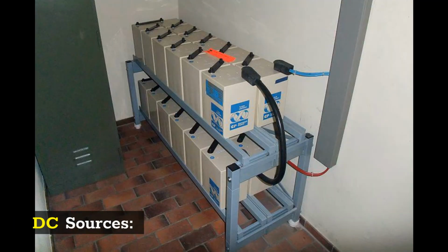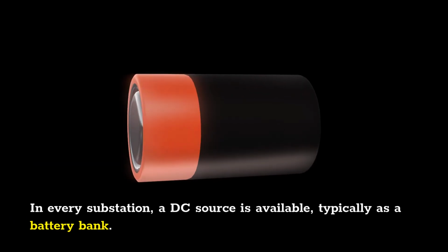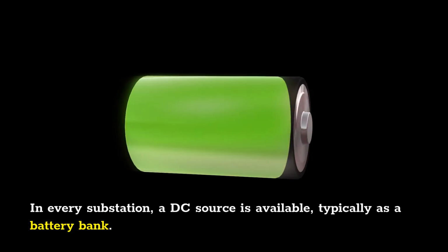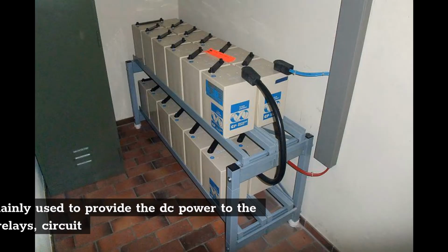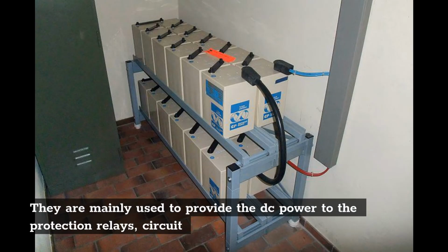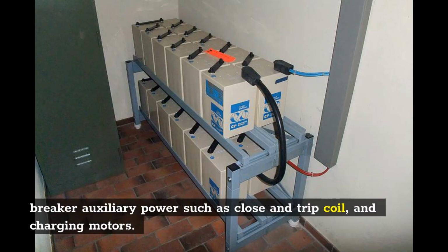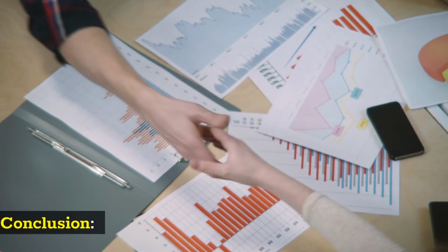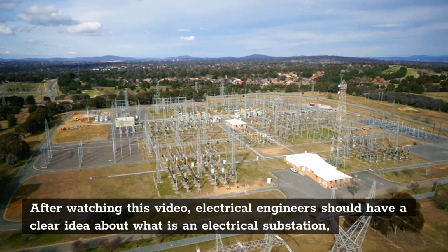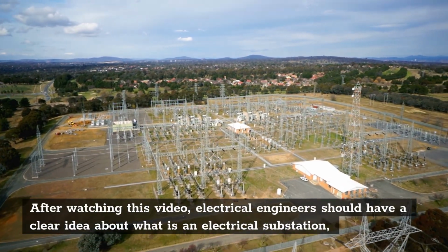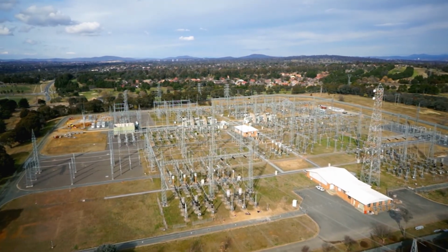DC sources. In every substation, a DC source is available, typically as a battery bank. They are mainly used to provide DC power to the protection relays, circuit breaker auxiliary power such as close and trip coil, and charging motors. Conclusion. After watching this video, electrical engineers should have a clear idea about what an electrical substation is and what its components are.